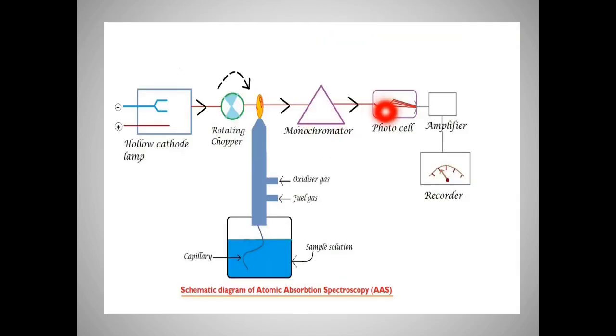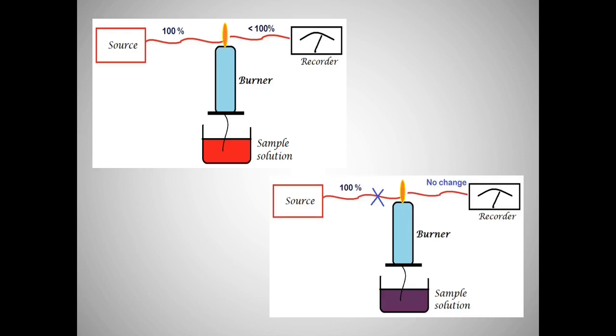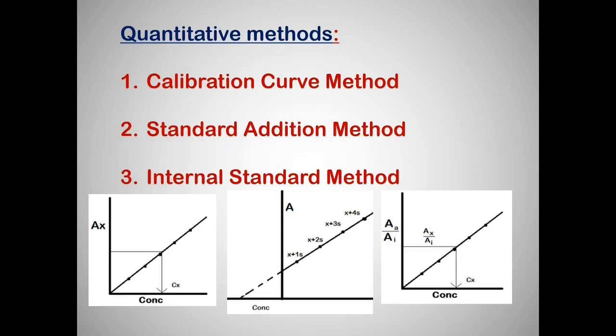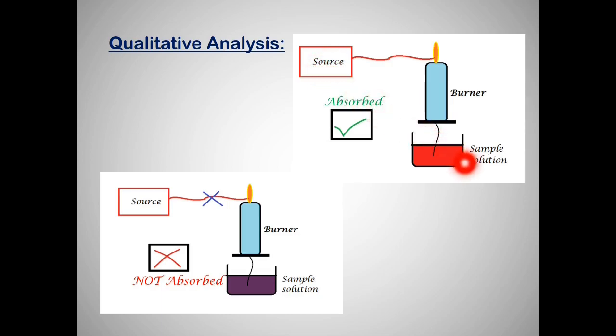The remaining components are the same as in flame emission spectroscopy. The recorder records the light intensity, and based on the change in intensity of the source radiation, we determine how much light has been absorbed — enabling quantitative analysis, done in the same manner as the flame photometer. AAS can also be used for qualitative analysis: if the source and the sample solution are the same element, light will be absorbed, confirming the identity of the sample.